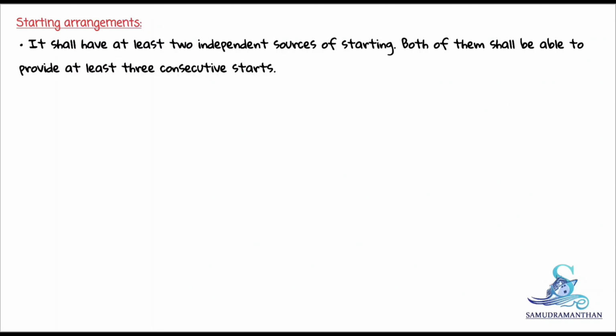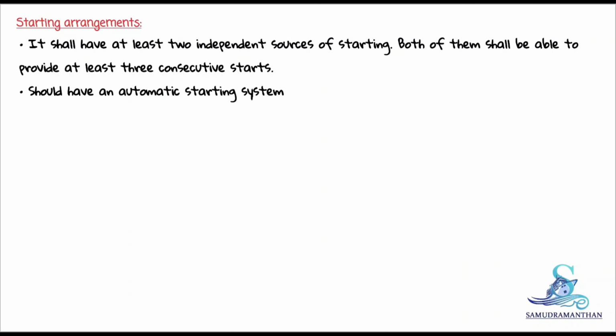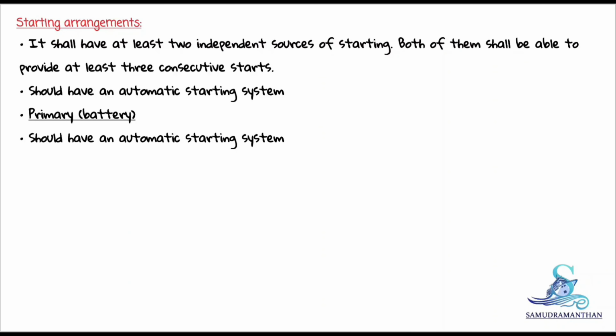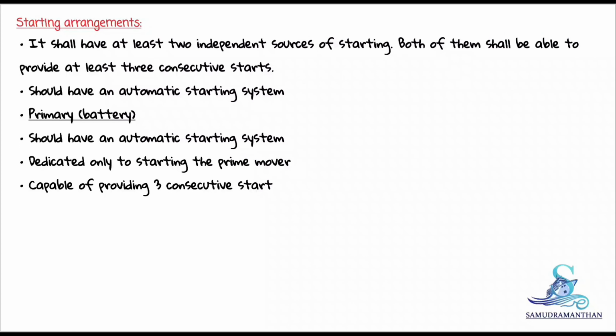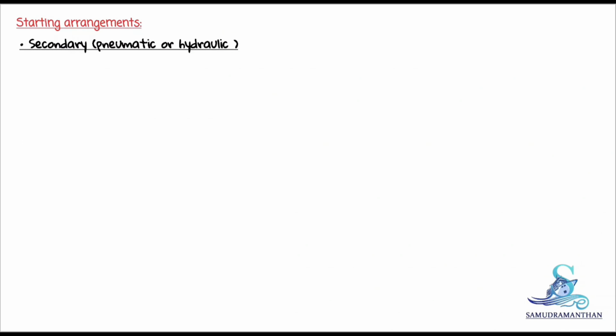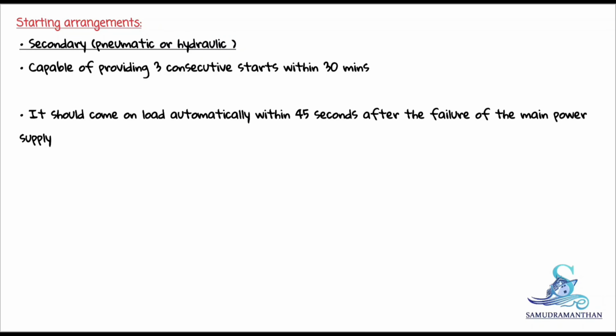Starting arrangements: it shall have at least two independent sources of starting. Both of them shall be able to provide at least 3 consecutive starts. Should have an automatic starting system. Primary: should have an automatic starting system dedicated only to starting the prime mover, capable of providing 3 consecutive starts. Secondary: capable of providing 3 consecutive starts within 30 minutes.